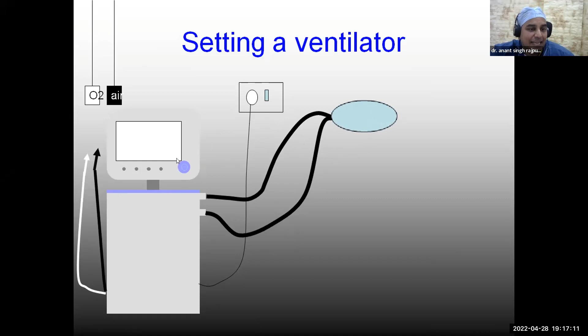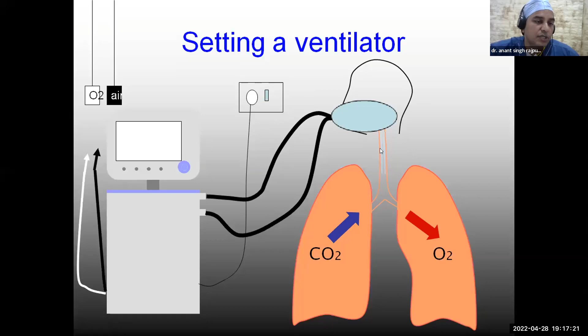Connect. The third step will be to connect the tubings with which you are going to ventilate the patient. The fourth step will be to check the ventilator by attaching a test lung. Okay? Once the test lung is working nicely, then attach the patient. Don't attach the patient and then try to see whether the ventilator is working nicely or not, or then ask what is wrong with the ventilator. So first you check the ventilator and then connect the patient to the ventilator.